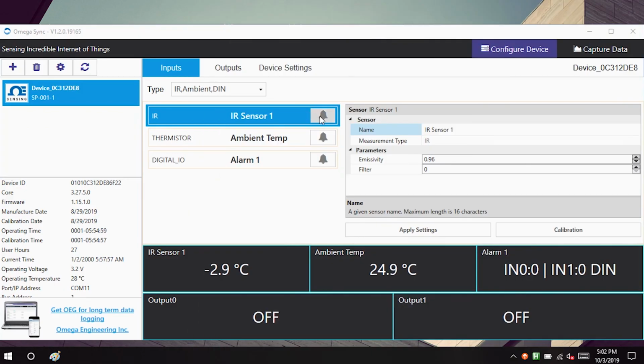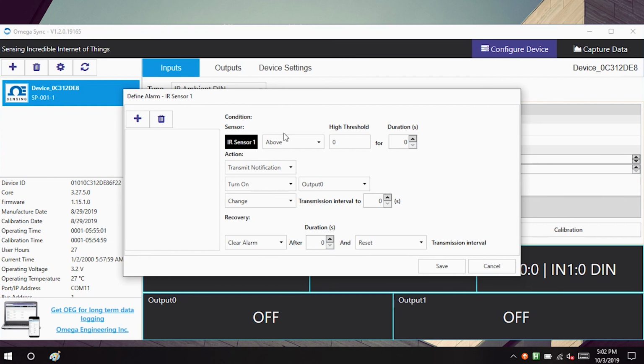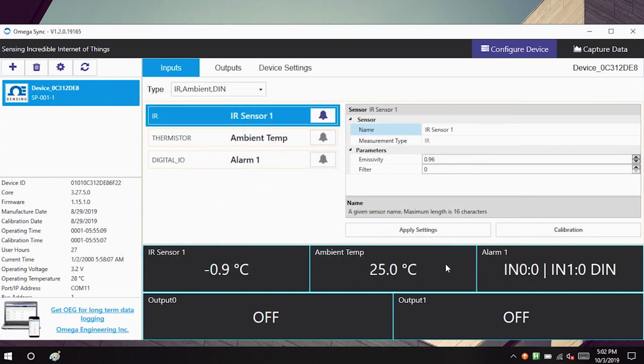Now let's set an alarm. Click the bell icon next to the input you'd like to customize. That will open the Define Alarm window where you can enter your threshold, let's say 5 degrees for a duration of 2 seconds, and then click Save to finalize.